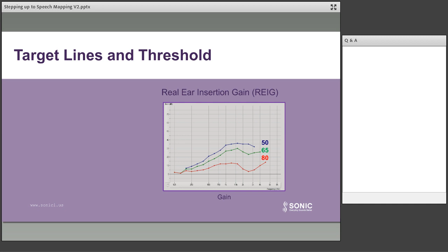screen looks like. Now when we come to the speech mapping screen, it's slightly different. We again have an 80, a 65 and a 50 curve, but now, because this is an REAR view, the 50 curve represents 50 dB of stimulus plus the gain, the 65 curve represents 65 stimulus plus the gain, and the 80 curve is 80 dB stimulus plus the gain. So you can see that the 80 curve's on the top, the 65's in the middle, and then the 50 is underneath. So it is the opposite to the view of insertion gain.